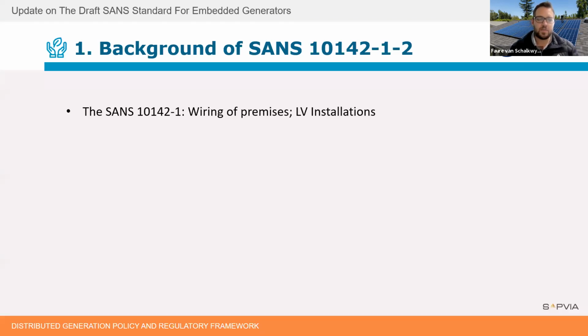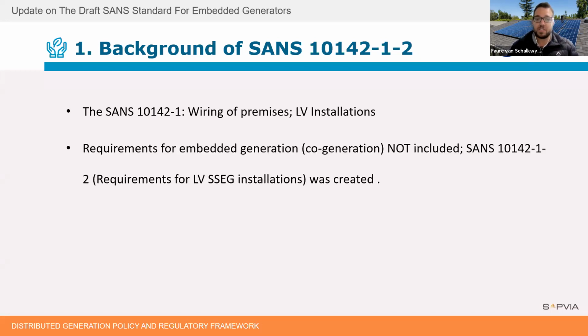First of all, the SANS 10142-1, for those who don't know, is the bible according to which electricians install or carry out electrical installation work. This specific standard covers the wiring of premises, so fixed installations, and it's for low voltage - low voltage meaning less than 1,000 volts AC or 1,500 volts DC. Anything beyond that, other standards start to kick in.